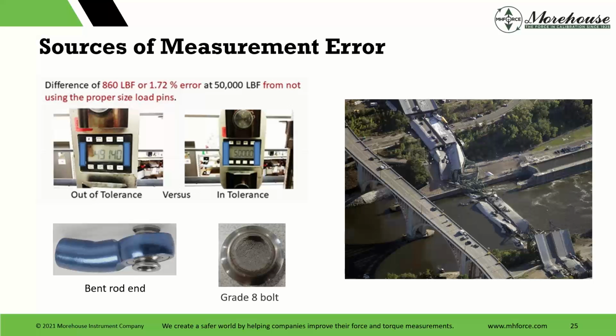So there's pin size. You can see in the picture on the left, 49-140. Remember I said 860 pound error earlier? That's 1.72% error on a 0.1% device, and that's from not using the proper load pins.